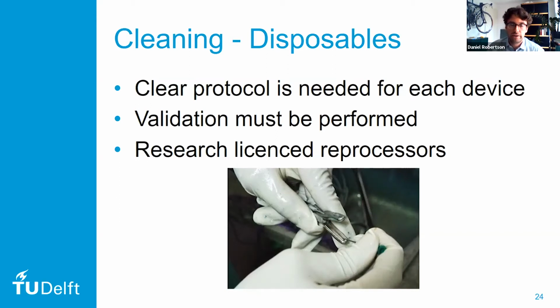Now, the difficulty in cleaning can be seen, and this is one nurse who's demonstrating how to clean a ligature instrument. And he actually needs to use a needle to get into the groove. Now, I'm not actually recommending that this is the best method for doing it, but we need a very clear protocol on how to clean these devices, and that protocol must be validated. So it should be checked. If you want to reprocess a device, really think about all the steps you have to take to safely reprocess it. And one thing you could look into is that there are some companies that offer reprocessing services of single-use devices. So you can send your ports or electrosurgical devices to them, and they will reprocess it for you.